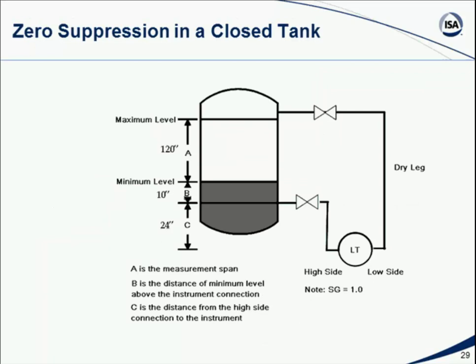Now, that's fine when we've got a tank that's vented to the atmosphere. Now, what about a tank that is, in fact, totally sealed and closed and pressurized, where there's going to be vapor exerting a pressure on the fluid in the tank? How do we read that? How do we correct for that? Well, we can use the same situation. Now, that low side leg of the level transmitter device, instead of being vented to the atmosphere, we pipe it up and bring it over and plug it back into the tank above the maximum fluid level. So that leg is called a dry leg, because in theory it has nothing in it except, shall we say, whatever the gas is that's above the liquid level in the tank. So as long as that leg is dry and empty, then whatever the pressure that is being generated by the vapor in the tank that's pushing down against the fluid in the tank, that same pressure is going through that dry leg and pressing against the side of the pressure transmitter that's doing the differential.